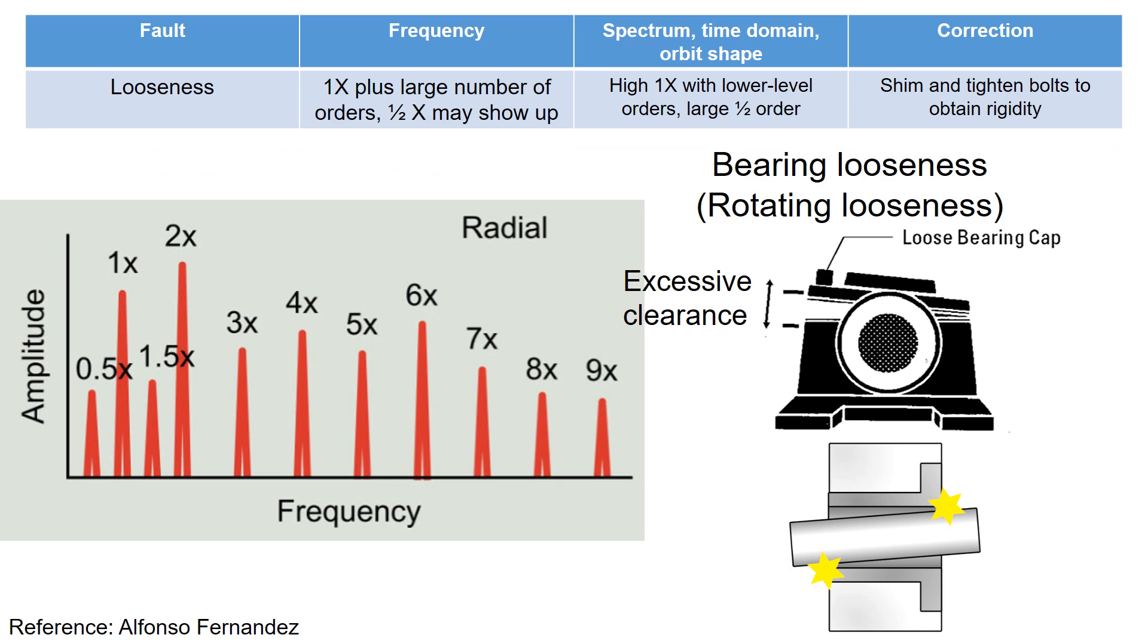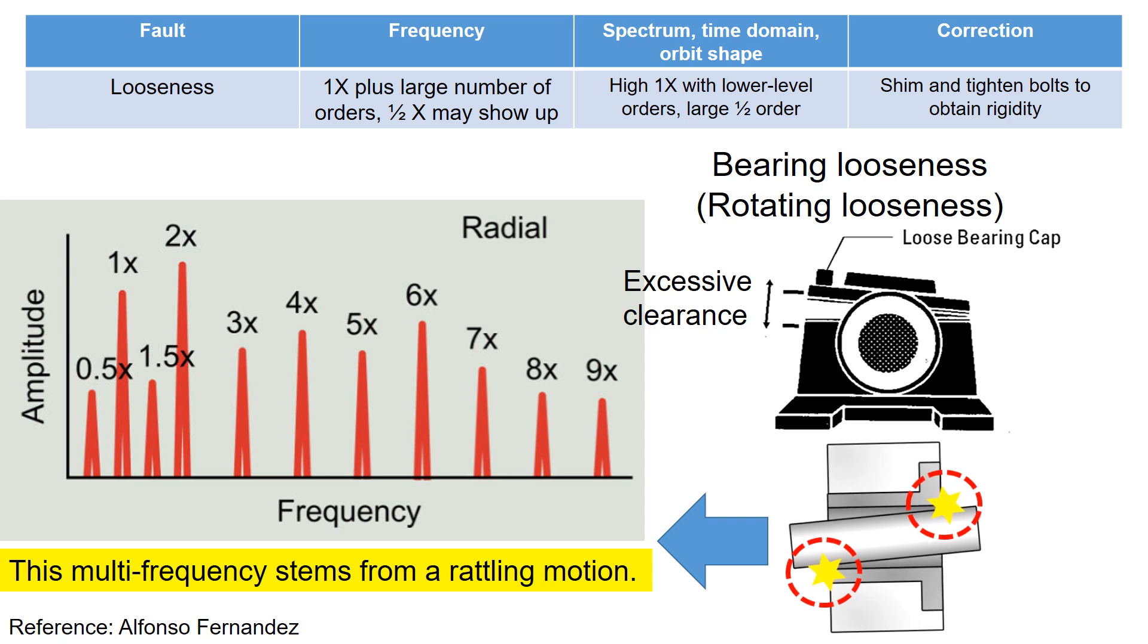Bearing looseness or rotational looseness can generate high order frequencies including 1x, 2x, 3x, and beyond. This multi-frequency stems from a rattling motion.